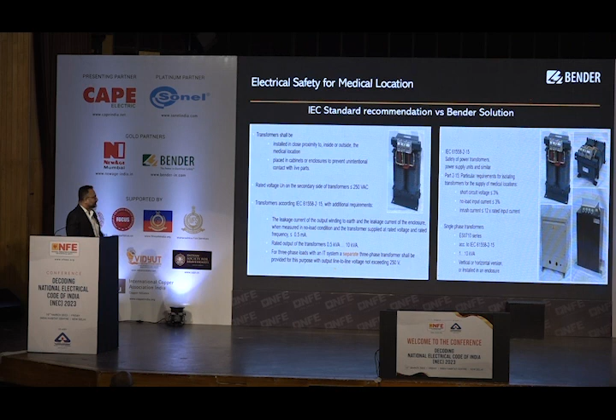So Bender is making that type of transformer, a very special, medical grade transformer. Then the insulation monitor: there has to be a special type of insulation monitor. We know the insulation monitor follows the IEC standard 61557-8, but the medical insulation monitor has to follow Annex C of that standard, where the threshold value of the insulation is 50 kilo ohms and the test voltage has to be 25 volts.